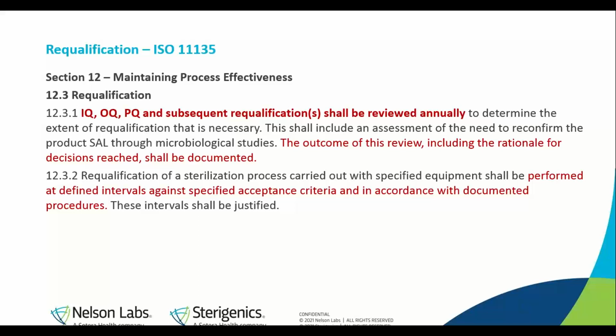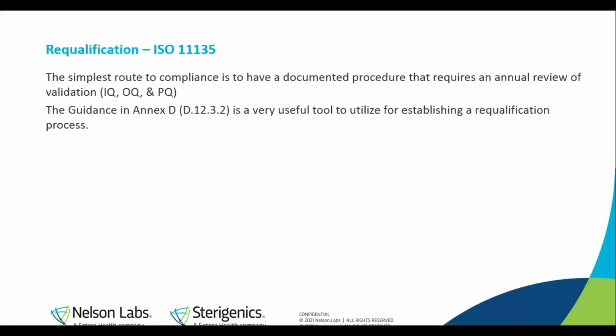Requalification of the process carried out with specific equipment shall be performed at defined intervals against specified acceptance criteria and in accordance with your documented procedures. These intervals shall be justified. So what this means is the simplest route to compliance is to have a documented procedure or work instruction that requires an annual review of the validation. And it should include IQ, OQ, and PQ.